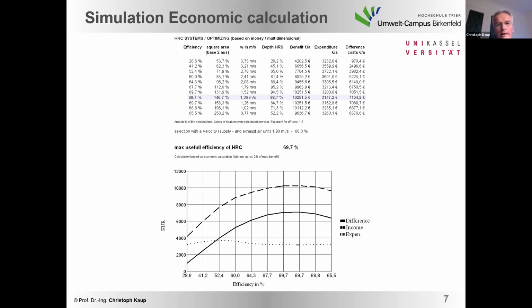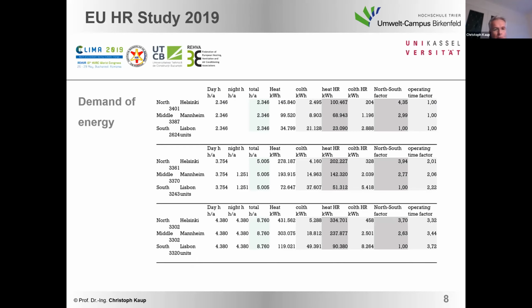That's the first point I would like to explain, but now my slide is hanging a little bit. It makes no sense to increase the heat exchanger more or to decrease the airflow, because if you are going too low with the airspeed, you will have problems with your heat transfer in your heat exchanger. So there is a clear optimum. And we used all these calculations in the first study, which we presented at the Klima 2019 in Bucharest, where we took more than 3,000 real units in calculation, built units with several types of heat exchanger, with run-around coils, rotors, plate exchangers, several air flows, sizes, etc.